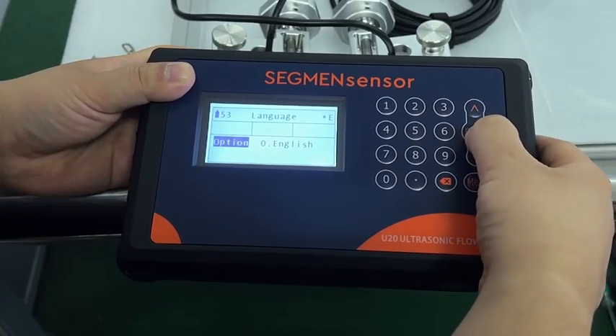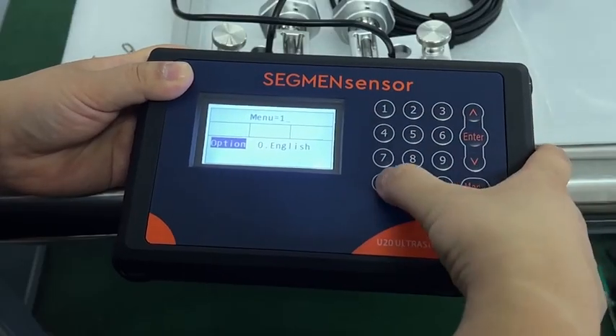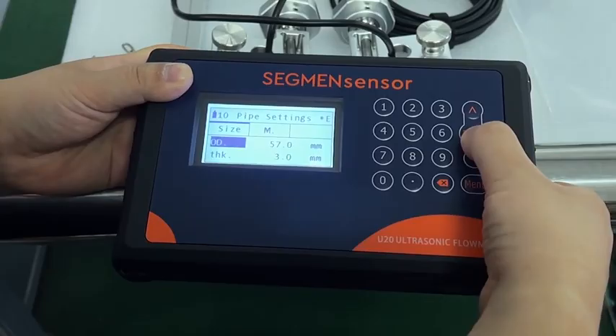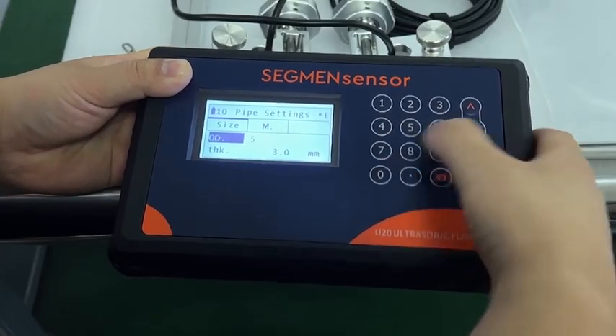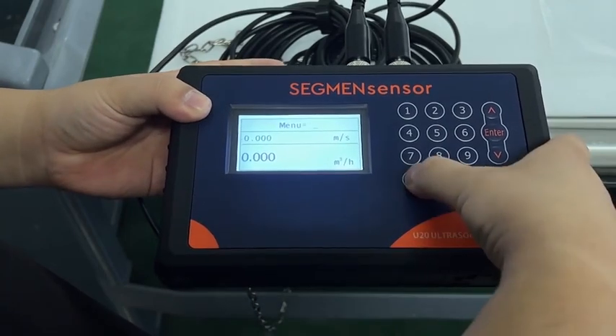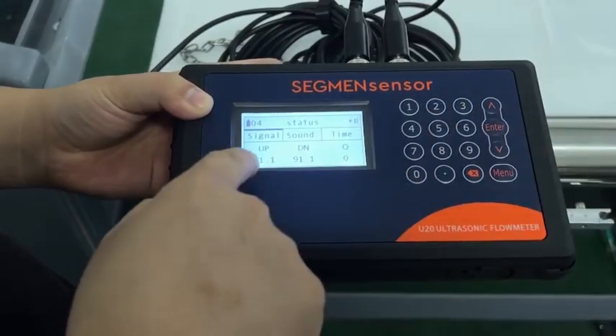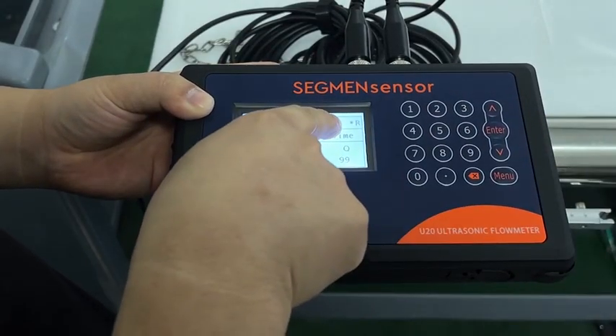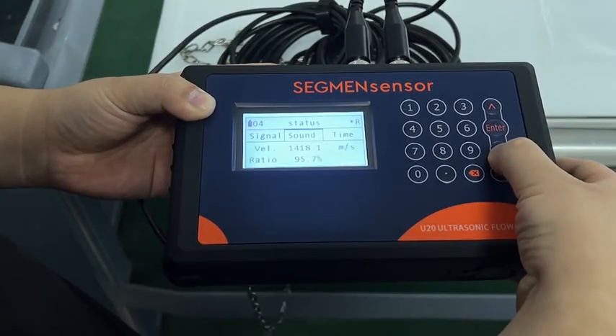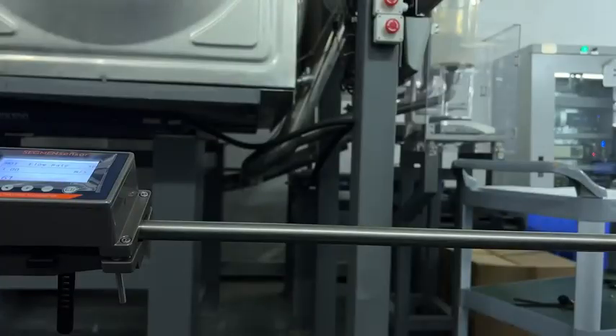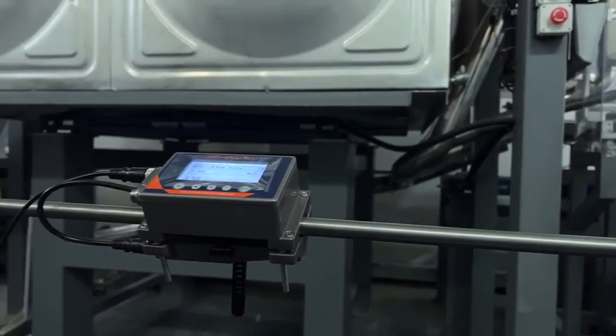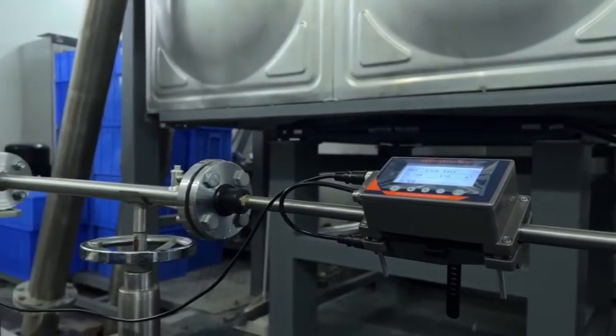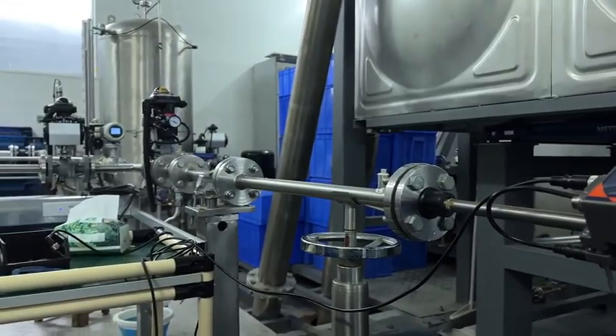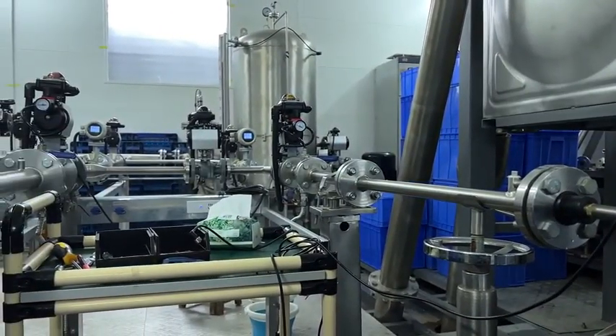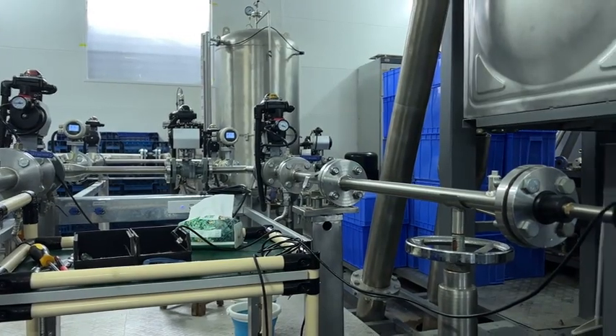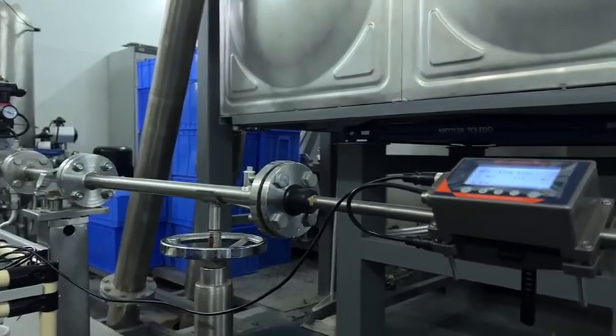Once parameters are confirmed, the calibration loop is started. The pump brings water up to the target flow rate. The reference meter measures the true flow rate independently. The SEGMEnSensor display shows its own measurement, and the two values are compared directly. Flow readings are stable and consistent. The display shows both instantaneous flow velocity in meters per second and volumetric flow rate in cubic meters per hour. Our calibration target is accuracy within plus or minus 1% of reading, and most units perform significantly better than this specification.